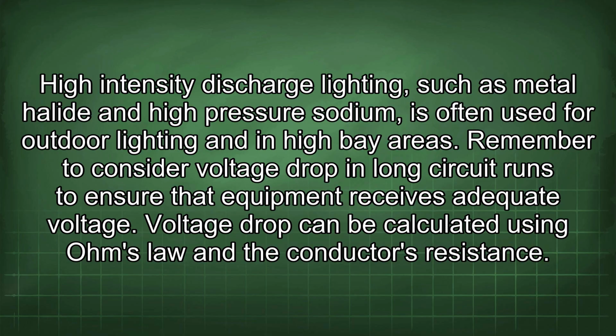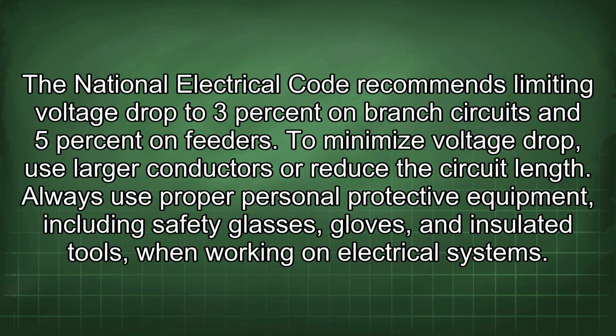Voltage drop can be calculated using Ohm's law and the conductor's resistance. The National Electrical Code recommends limiting voltage drop to 3% on branch circuits and 5% on feeders. To minimize voltage drop, use larger conductors or reduce the circuit length.